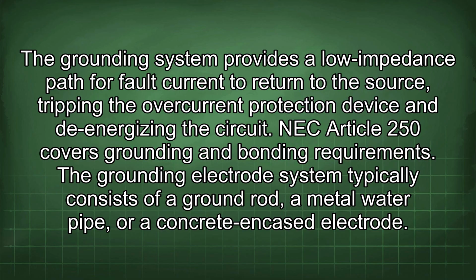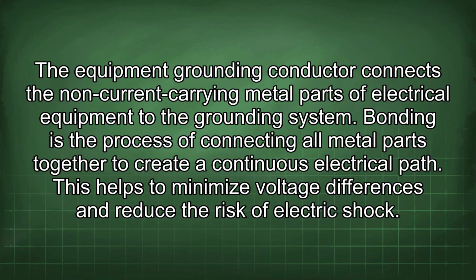The grounding system provides a low impedance path for fault current to return to the source, tripping the overcurrent protection device and de-energizing the circuit. NEC Article 250 covers grounding and bonding requirements. The grounding electrode system typically consists of a ground rod, a metal water pipe, or a concrete encased electrode. The equipment grounding conductor connects the non-current carrying metal parts of electrical equipment to the grounding system.